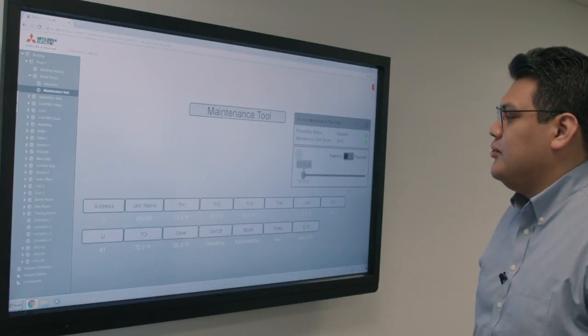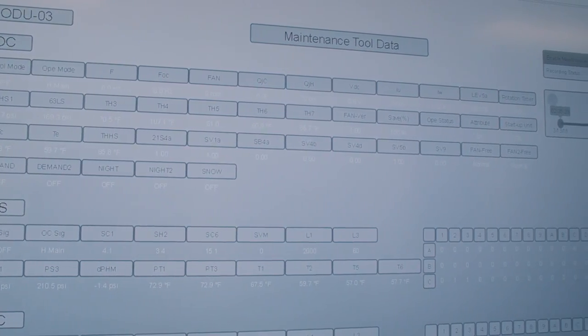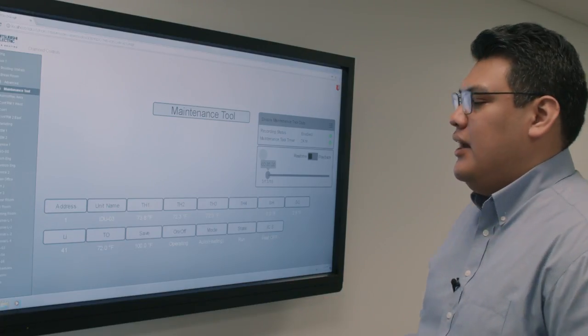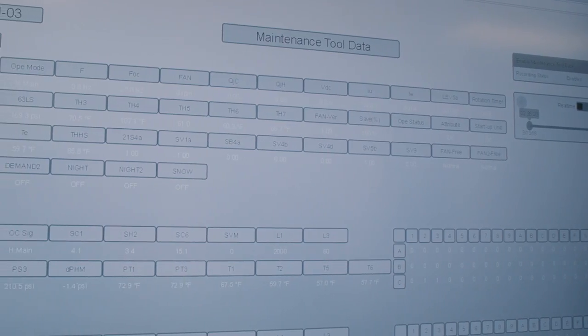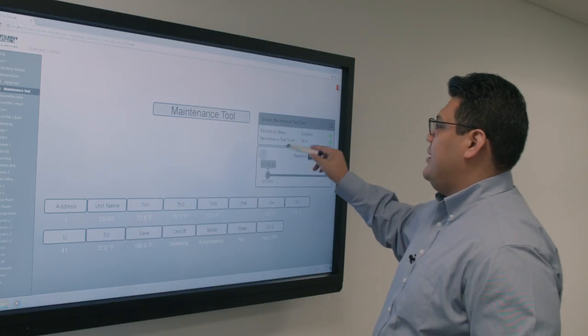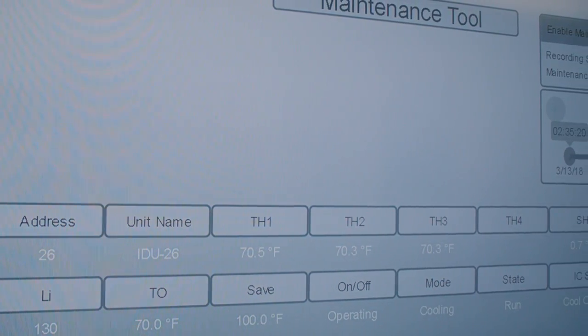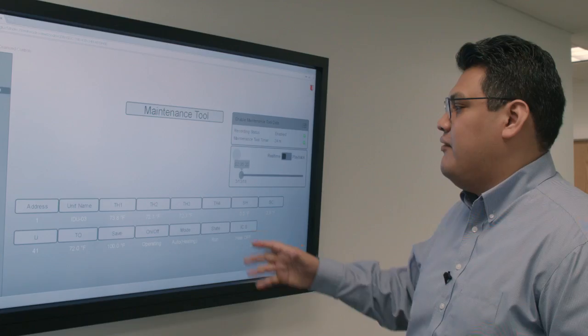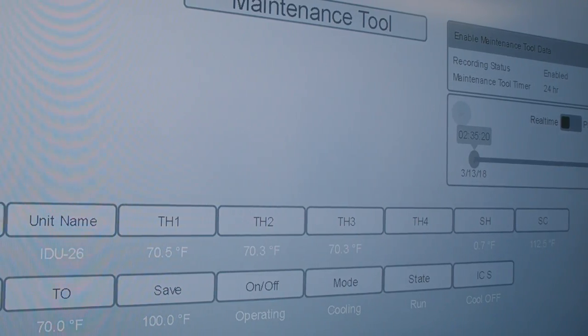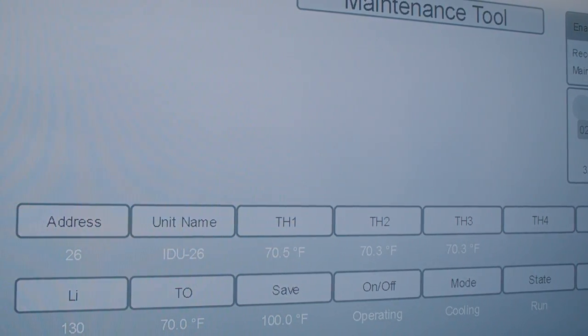Clicking on that, I can see the maintenance tool data. Maintenance tool data is typically data that is only visible to contractors and people servicing or maintaining the equipment, but here you can easily export that and make it visible via the advanced BACnet capability of our Diamond controls. You can record and capture data for the different temperatures. A trained contractor can easily identify issues by looking at operating temperatures, mode, runtime, and things like that to diagnose whether there's an issue or potentially could be an issue with the system.